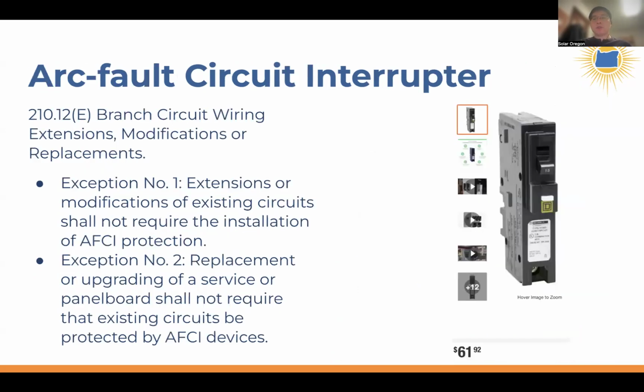Arc fault circuit interrupters - this idea is okay. If you hang a picture and the screw or nail pierces an electric wire inside the wall, you might get arcing, and that can burn your house down. Arc fault circuit interrupters are programmed to detect an arcing electrical situation and shut that branch circuit off to protect your house. Oregon did not make this a requirement.